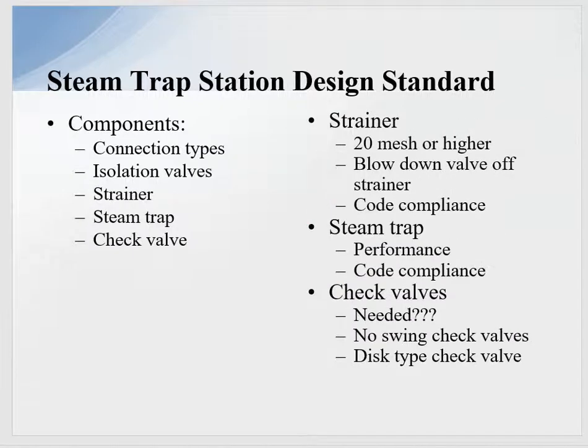The next thing on the steam trap station design: strainer. Anytime you put in a steam trap, you have to have a strainer ahead of it. The number one failure with steam traps is corrosion material getting into the steam trap. Stop the corrosion material from getting in and you have longevity. Any steam trap at 250 psi today should last 15 years. Strainer 20 mesh or higher. When you put a strainer in, put a block valve on the strainer so people can blow the strainer out. Make sure it's code compliant.